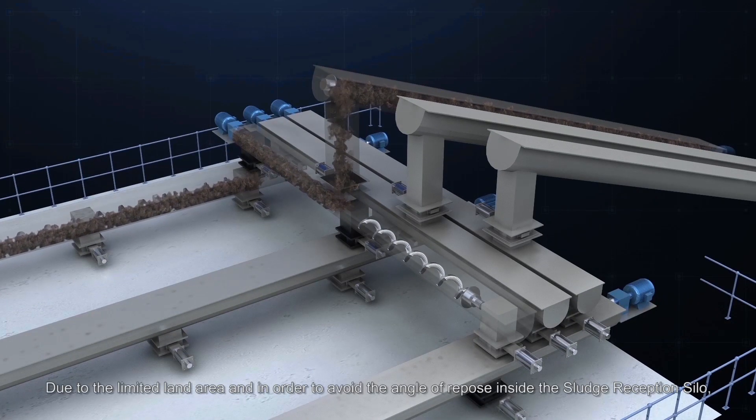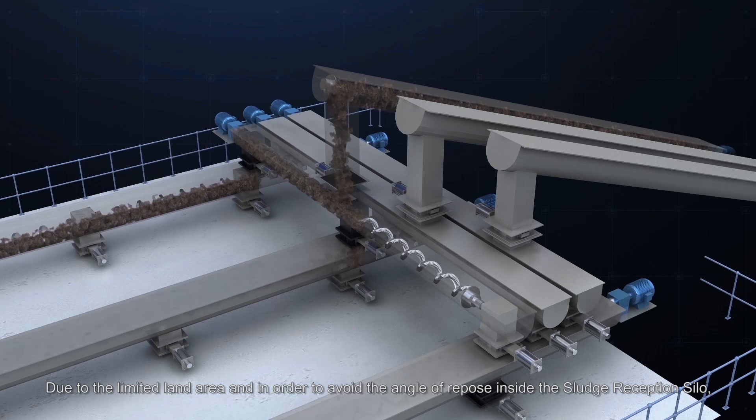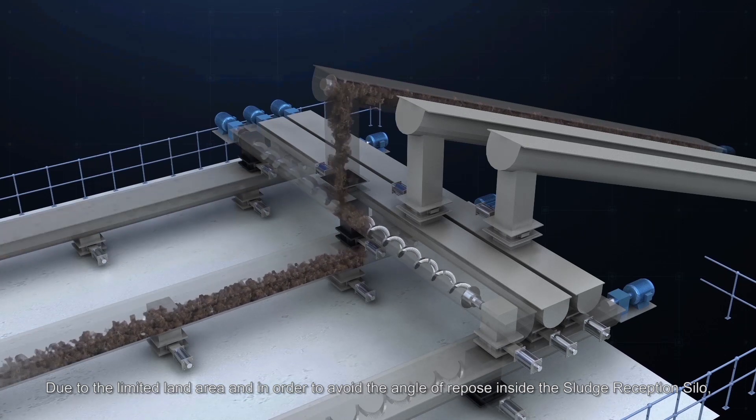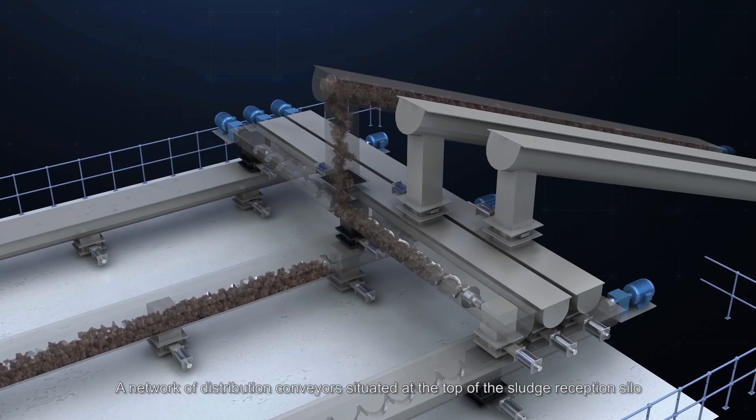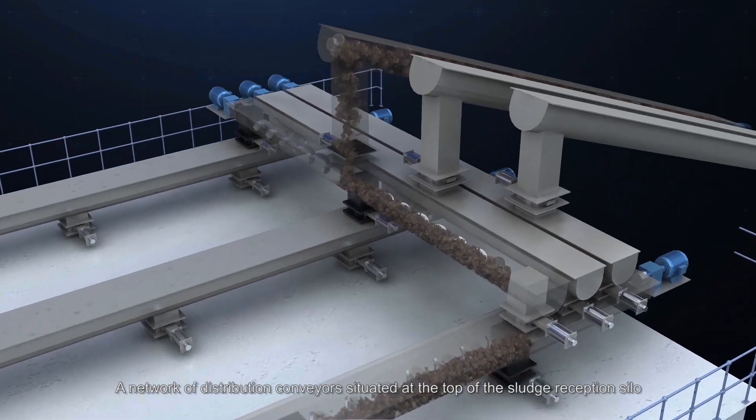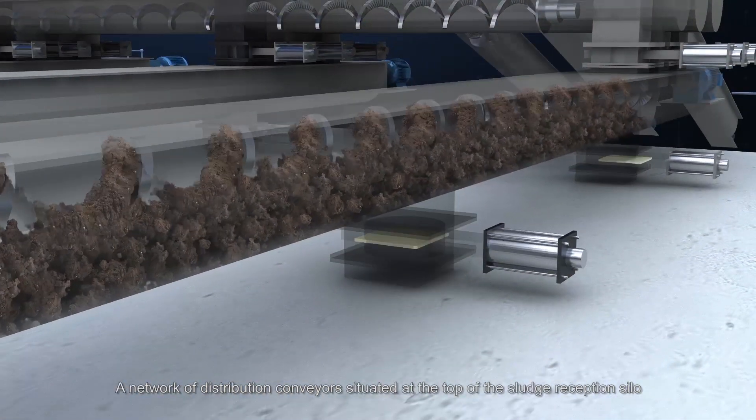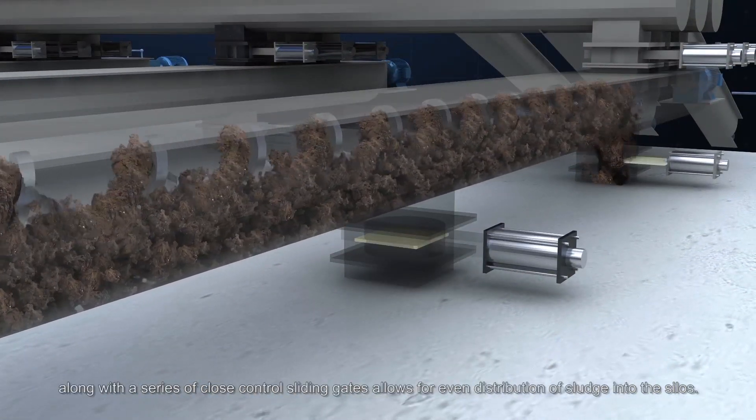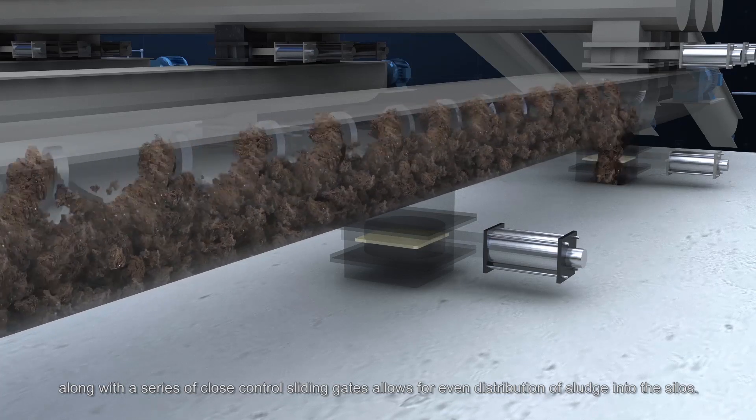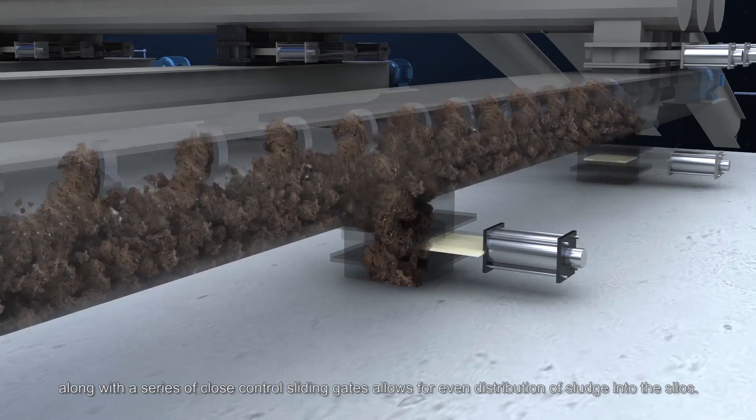Due to the limited land area, and in order to avoid the angle of repose inside the sludge reception silo, a network of distribution conveyors situated at the top of the sludge reception silo, along with a series of close control sliding gates, allows for even distribution of sludge into the silos.